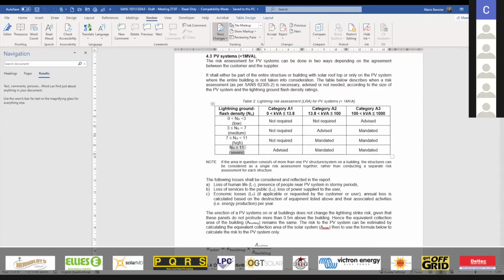Looking at the most common systems nowadays, categories A2 and A3, in areas like Cape Town it's still not required because we understand the risk there, and because 10142 part 1 and part 2 mandate the SPD on the DC side plus shielding of cables - this is already enough to mitigate risk in low lightning areas.